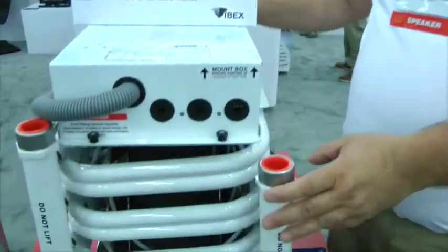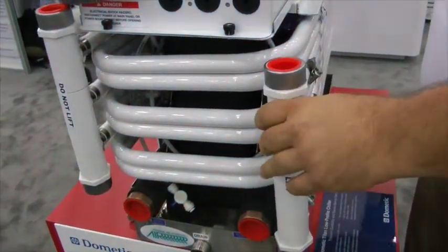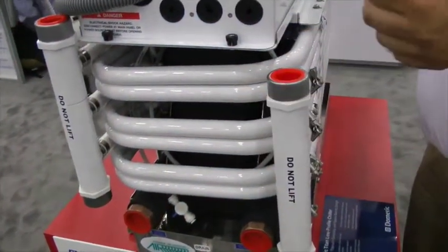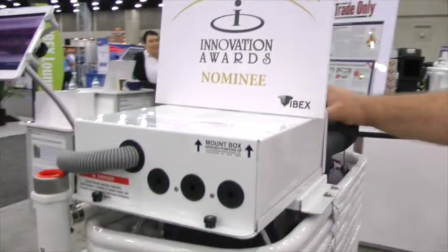This week at IBEX we showed our new 5-ton chiller with a titanium condenser coil. In the industry, a coaxial copper-nickel coil is typically used. The copper-nickel is very susceptible to erosion and corrosion, and also due to chemical cleaning, it attacks the condenser aggressively. The titanium will hold up much better to the chemicals and the velocity of the water and allows less growth to happen inside the condenser coil itself.